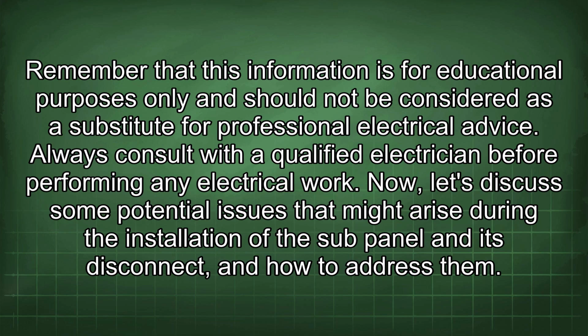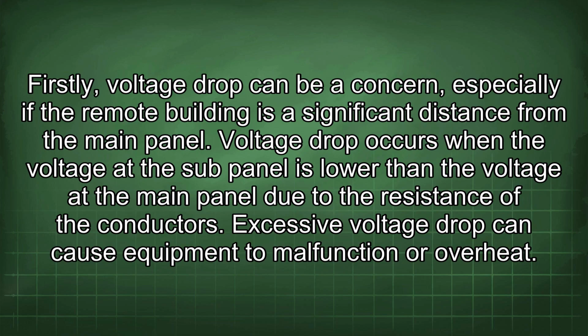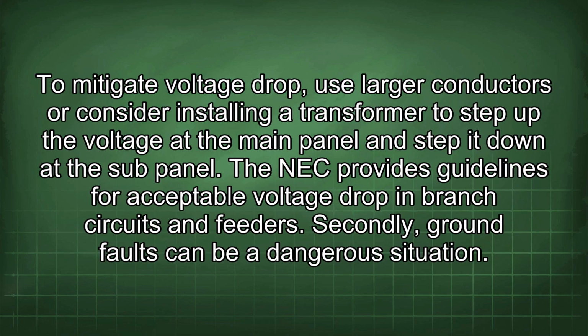Now, let's discuss some potential issues that might arise during the installation of the sub-panel and its disconnect, and how to address them. Firstly, voltage drop can be a concern, especially if the remote building is a significant distance from the main panel. Voltage drop occurs when the voltage at the sub-panel is lower than the voltage at the main panel due to the resistance of the conductors. Excessive voltage drop can cause equipment to malfunction or overheat. To mitigate voltage drop, use larger conductors or consider installing a transformer to step up the voltage at the main panel and step it down at the sub-panel. The NEC provides guidelines for acceptable voltage drop in branch circuits and feeders.